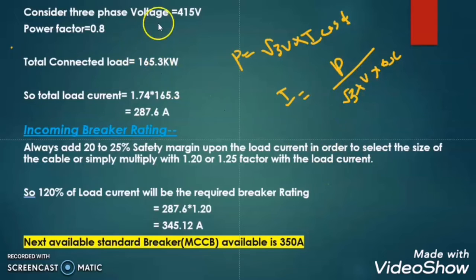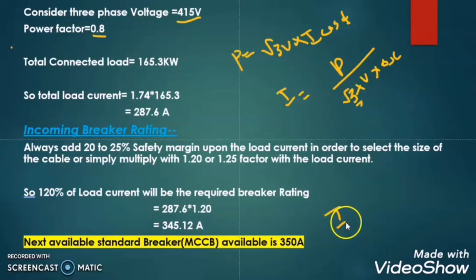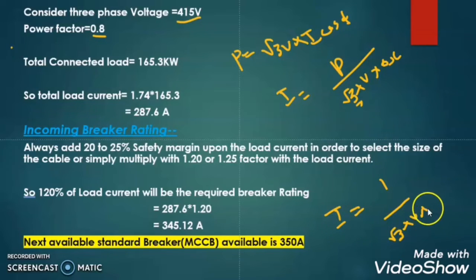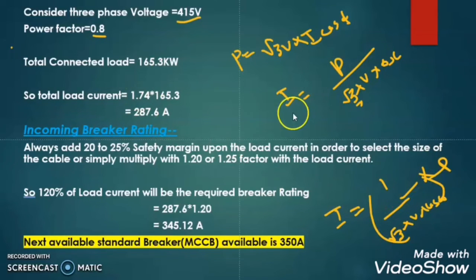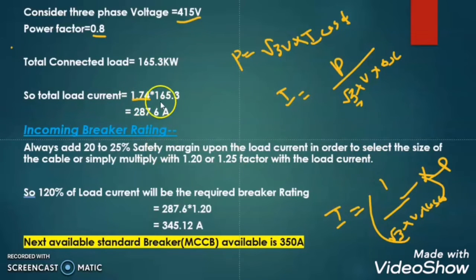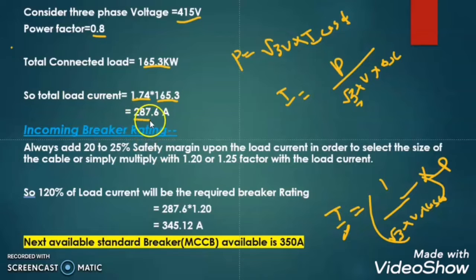Here you see that I took the fixed value of voltage that is 415V and the power factor is 0.8, and √3 is constant. So I = 1 ÷ (√3 × V × cos φ) × power. If we substitute and simplify, we get the constant 1.74. Multiplying with the total load connected, we get the total current as 287.6 Ampere.